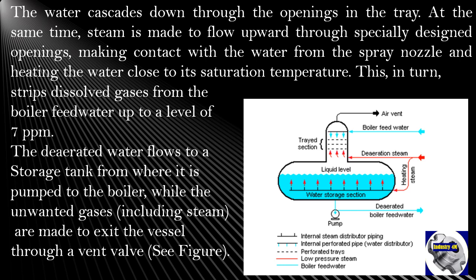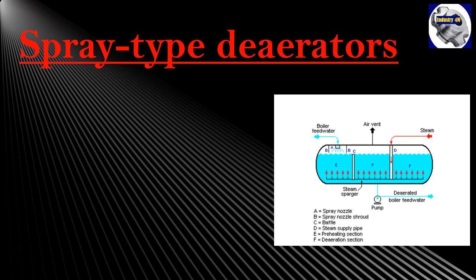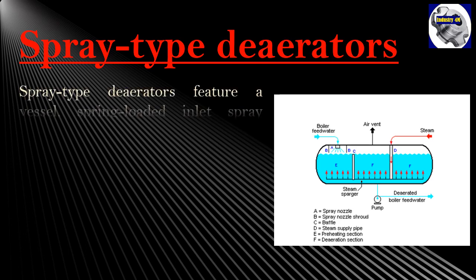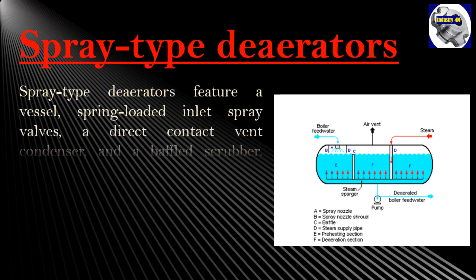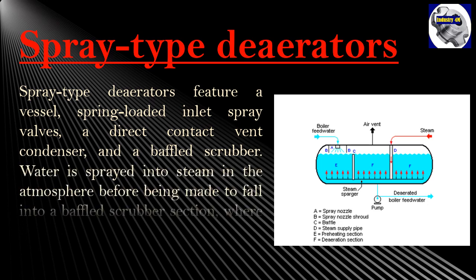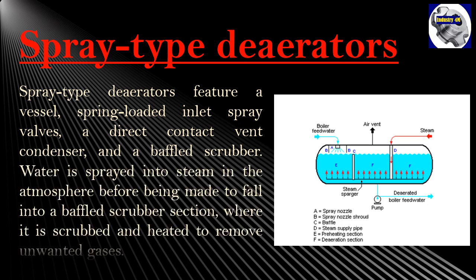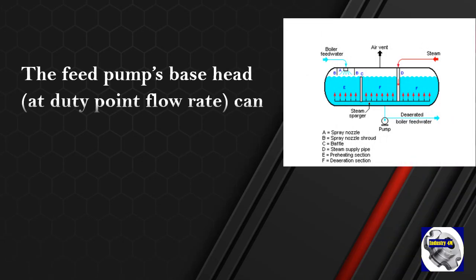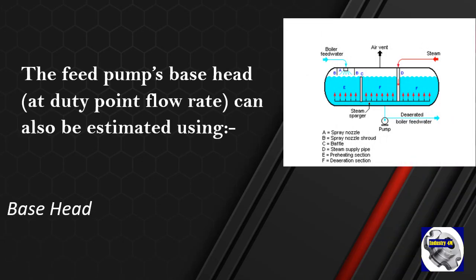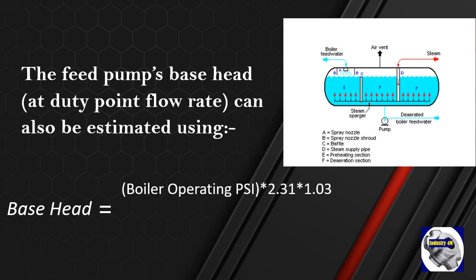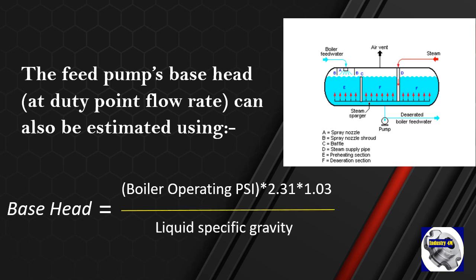Spray-type deaerators feature a vessel, spring-loaded inlet spray valves, a direct contact vent condenser, and a baffled scrubber. Water is sprayed into steam in the atmosphere before being made to fall into a baffled scrubber section, where it is scrubbed and heated to remove unwanted gases. The feed pump's base head can also be estimated using this formula: Base head = (Boiler operating pressure × 2.31 × 1.03) ÷ liquid's specific gravity.